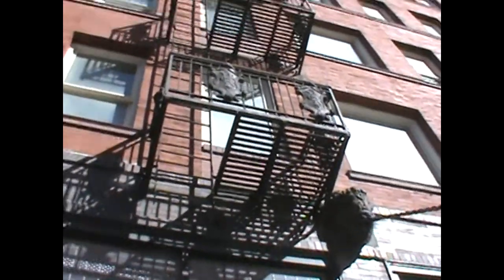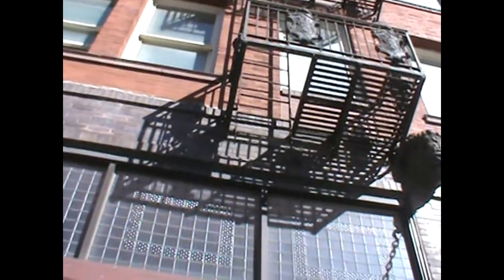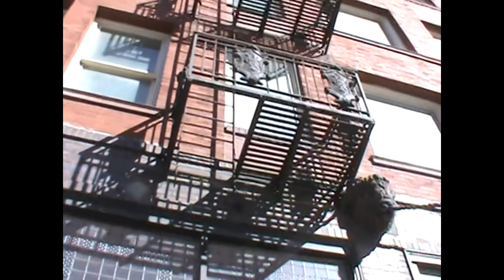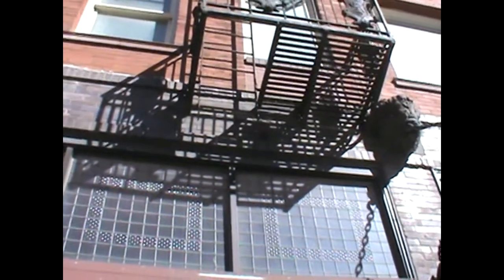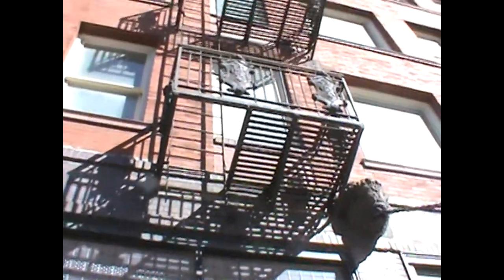Has it been kept painted? Must be structurally sound. Must be kept painted. Has this one been kept painted? Nope. So right there is the origination of a violation. Correct. Who's going to tell you what's structurally wrong with this? Again, a professional. Third party, right? Yep. Structural engineer, registered architect, or others acceptable to the building official or fire official.